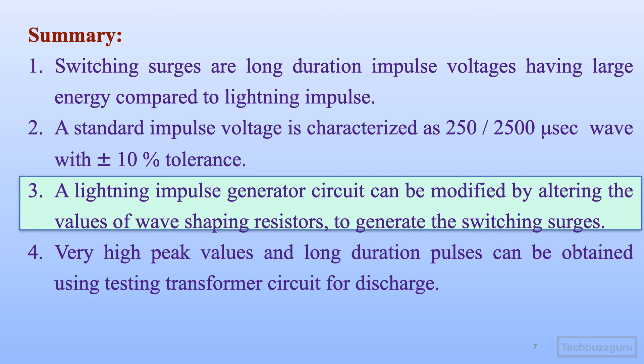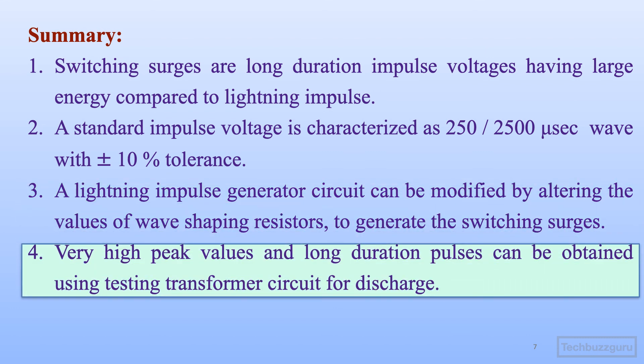The lightning impulse generators can be modified by altering the values of wave shaping resistors to generate switching surges, so no different circuit is required. And lastly, very high peak values and long duration pulses can be obtained by using a circuit that utilizes testing transformers for the purpose of discharge through the test object. This way the topic on generation of switching impulse voltages is covered through this video.